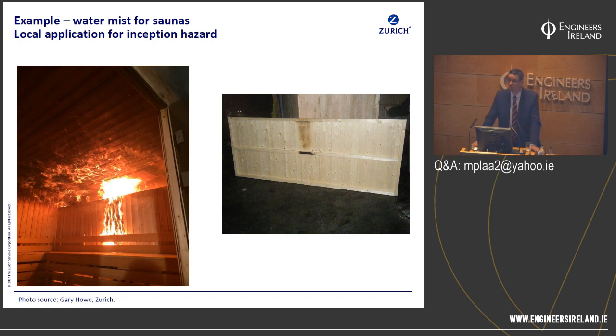And we get approached with systems of stored pressure systems, a variety of systems from different manufacturers. And we've actually had failures of water mist systems in this particular application. And you can see from the photograph, in less than 5 minutes, you can get to flashover in a timber sauna. This is a test that I undertook at a fire test lab to see actually what would happen in a timber sauna. How quick could we get to flashover?